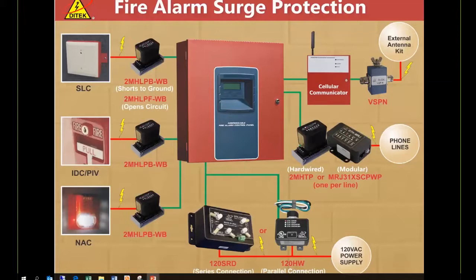Fire alarm surge protection. These are the different products that we do offer in a fire alarm circuit. Of course, the 120 volt feed coming in. We offer a product, the 120 SRD, which is a series device rated at 20 amp with dry contacts. And then we also offer a parallel device, the 120 HW, which is in parallel, so it is unlimited current. That will protect your 120 volt feed, as well as the deflector, as we showed earlier.